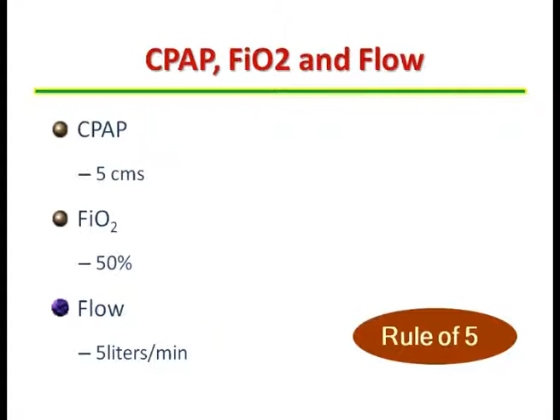Once you start the baby on CPAP, subsequently the flow is titrated to get minimal bubbles in the bubble chamber in a bubble CPAP. For giving a pressure of 4 centimeters to 7 centimeters, the average flow requirements vary from 2 to 7 liters per minute. If the flow requirement is more than 7 liters, check for leaks in the circuit. For a baby started on CPAP on a ventilator, usually the flow rates would vary from 6 to 8 liters per minute.